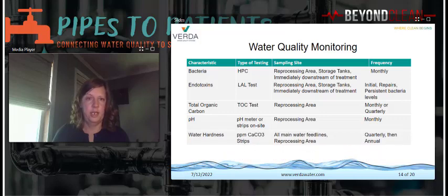If you notice, endotoxin testing is only required for initial validation and after any repairs or persistent bacteria levels. Total organic carbon is recommended for monthly or quarterly testing, depending on your site. pH is a test done monthly, and water hardness is recommended quarterly until a baseline is established, and then annually thereafter.